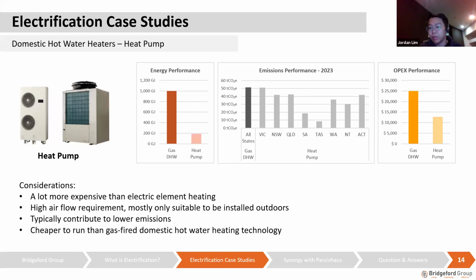Heat pump for domestic hot water applications, on the other hand, can save up to 80% in energy. And because of this, it actually has a positive impact in reducing the emissions for domestic hot water systems, because it's just so much more efficient and the operating cost is also less. This does come with a bit of a drawback. It is, however, significantly more expensive than electric element heating. I can't really pull a figure off the top of my head, but for systems that can be electrically powered, the same capacity of a system is probably at least 3 or 4 times more expensive. So that's why historically it's not necessarily a very favorable technology.